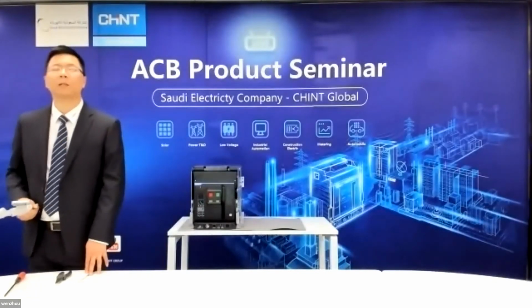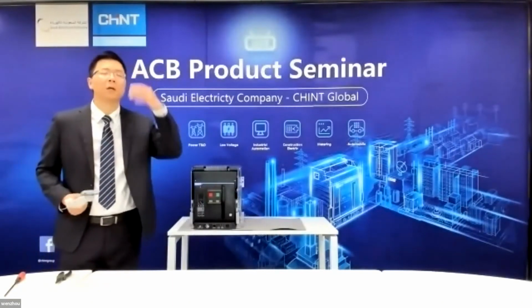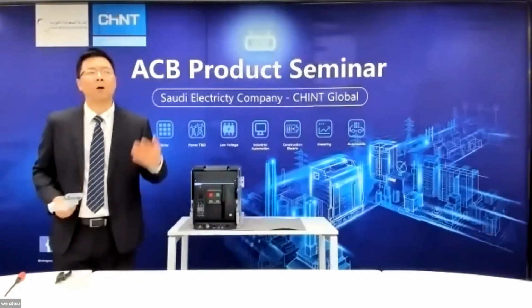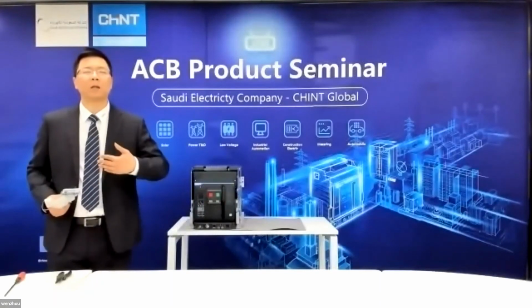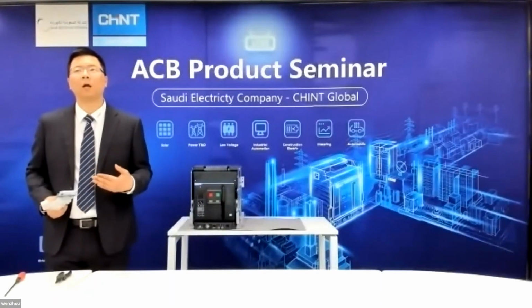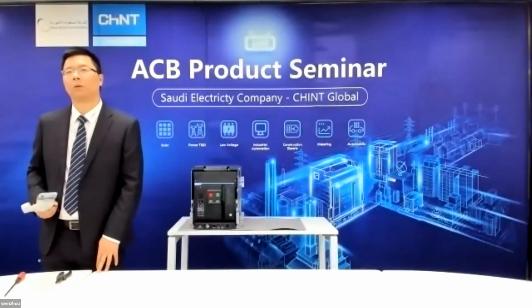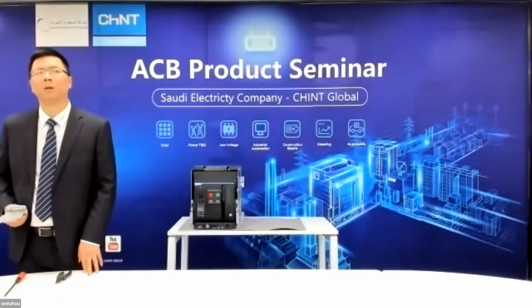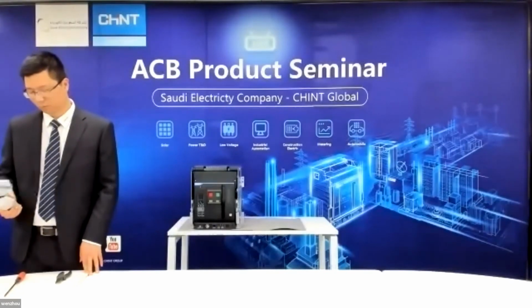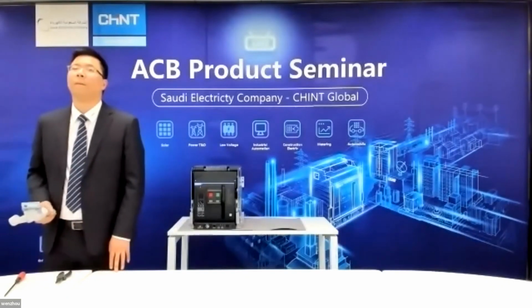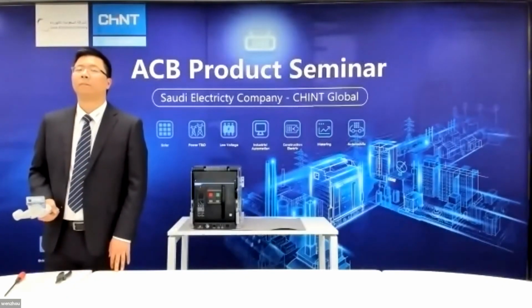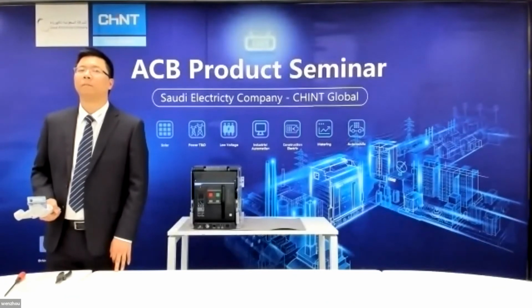Mr. Walid, yes, I know it's clear for the question - you mean the system has some harmonic and all ACBs, how do they protect themselves so as not to mix it up. No - it means distinguishing between harmonics and the earth fault. Because we encountered a problem in a data center, the earth leakage trip unit or the earth leakage component is regarding or considering the harmonics as earth fault.